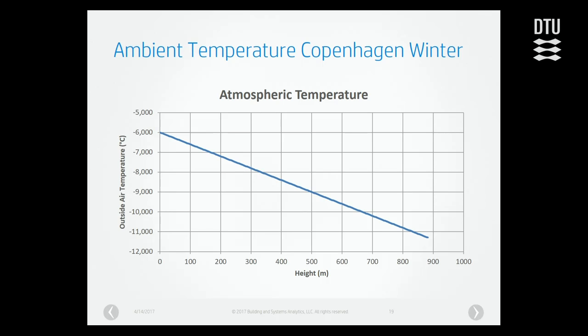Here it's minus 6. Previously I was in Delhi, which starts off at 6 degrees, but gets near three below freezing as you go up a building, which a majority of engineers don't understand, because what happens to the system? You're confused - at ground level it's fine, and then I go up 600 meters and I've got freezing in my pipes. Coming from Denmark, you know you don't want freezing in your pipes, do you? Because that's bad.